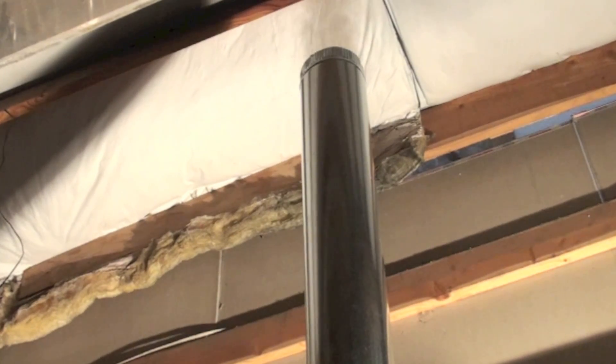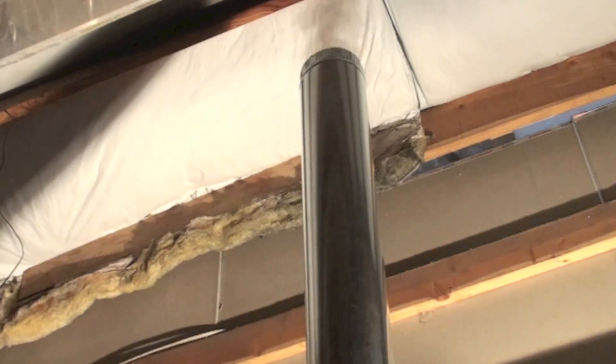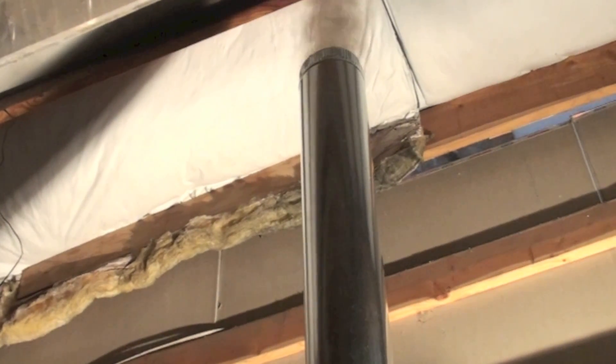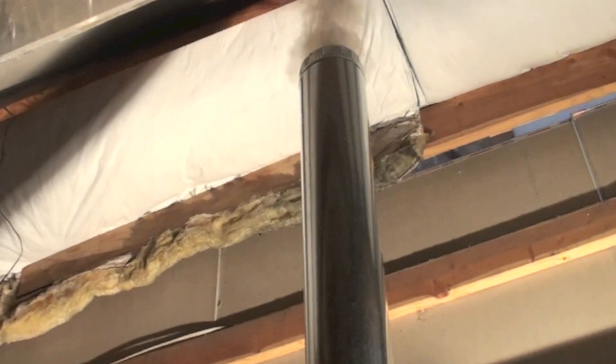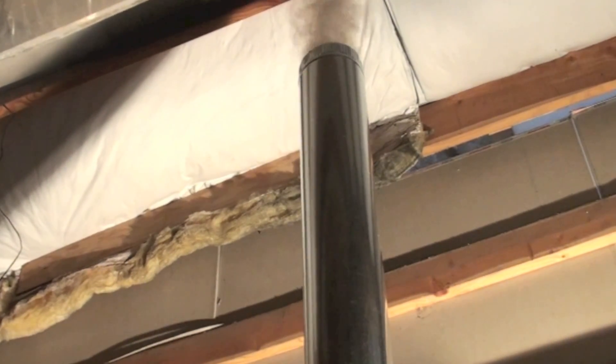I want you to notice there's black smoke coming out of there. That's because I've cut the air down so it's easier to see. I'm going to go ahead and cap that off like it was plugged and let's see what happens.